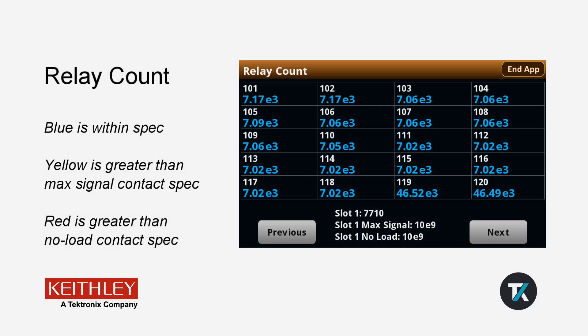The Relay Count app looks at what cards are inserted in the instrument. It then queries inserted cards for relay closure counts on each channel. The app compares these values to the card's Relay Closure Count specifications and outputs the closure count as a color-coded number.